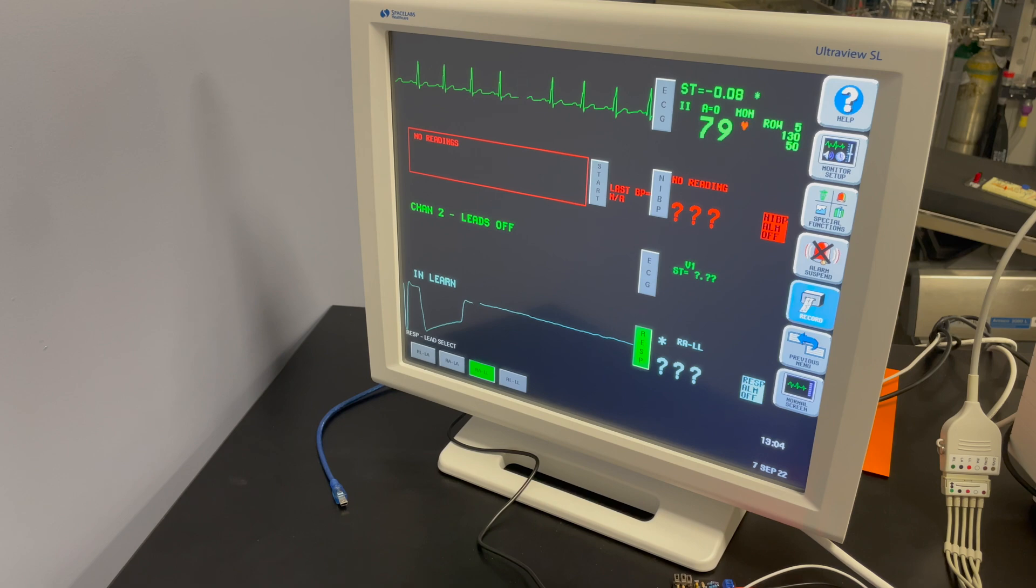After a bit, that's going to give us enough information to determine the respiratory rate or to simulate the respiratory rate. So that's really important. The respiratory rate is only simulated between the RA and LL leads, so you're going to have to make sure you set up whatever device you're using so that that's correct.